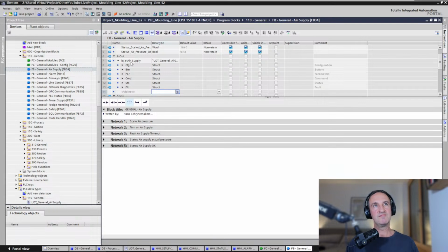One thing lately that I'm thinking more about is that an in-out is smart and saves resources, but the big disadvantage of using an in-out is that it's difficult to troubleshoot, because if you use one of these tags right here in the logic and it's used somewhere else in your logic, it cannot cross-reference through the in-out in TIA portal.